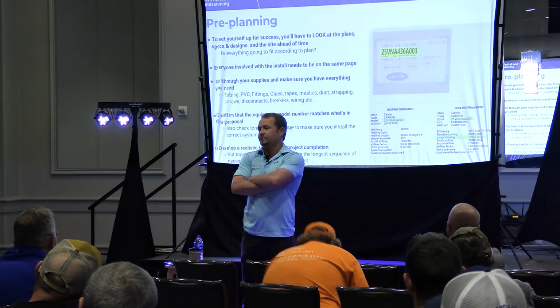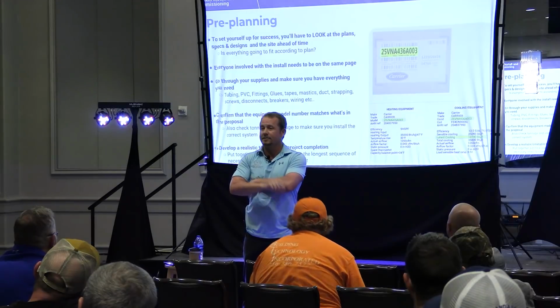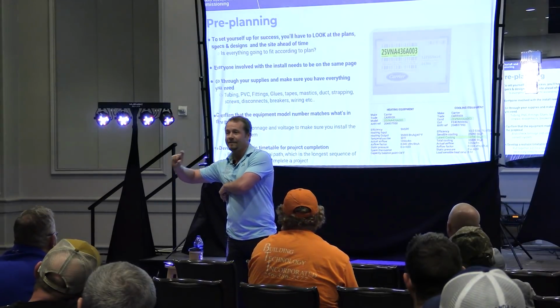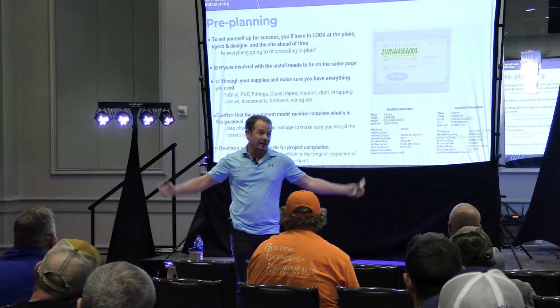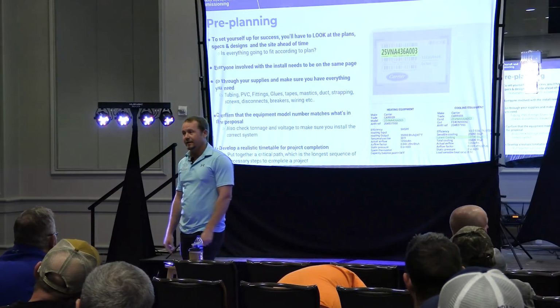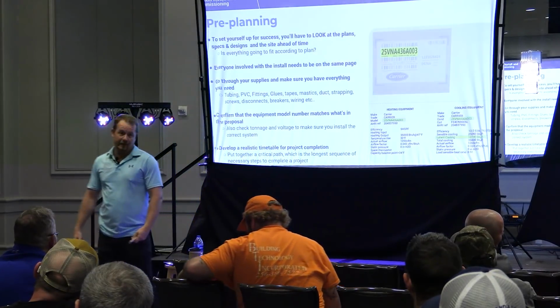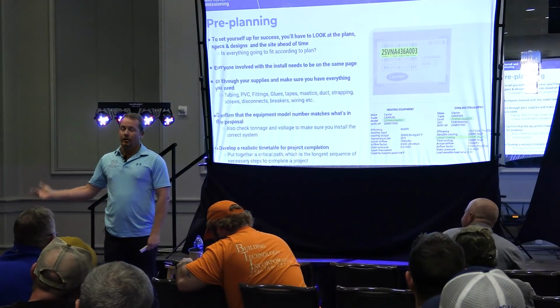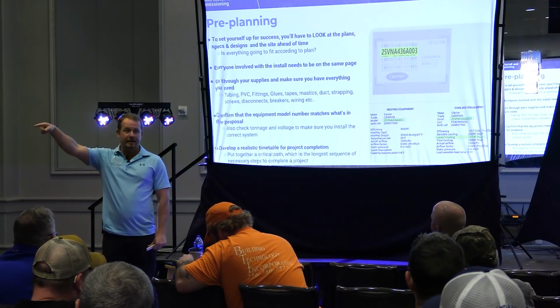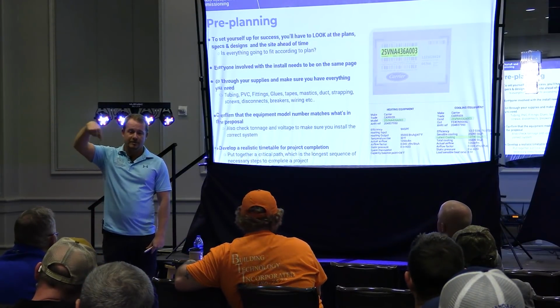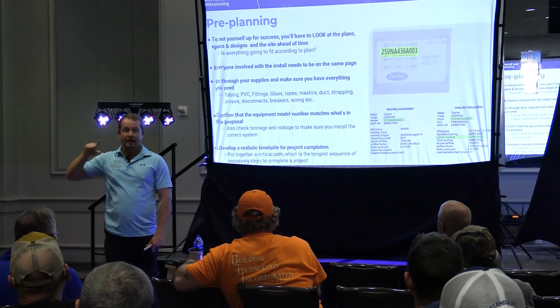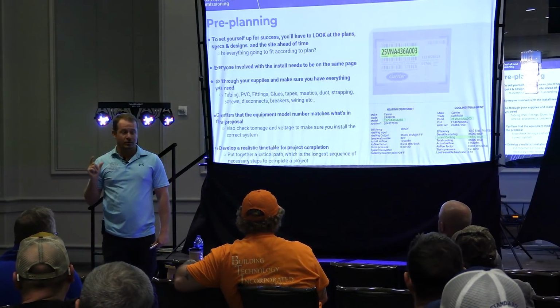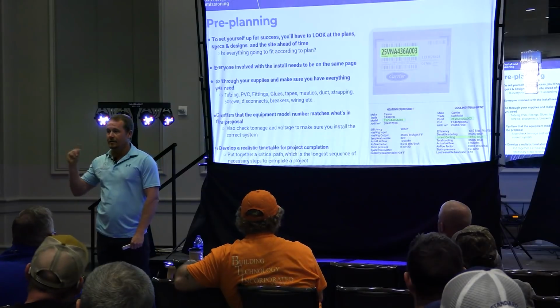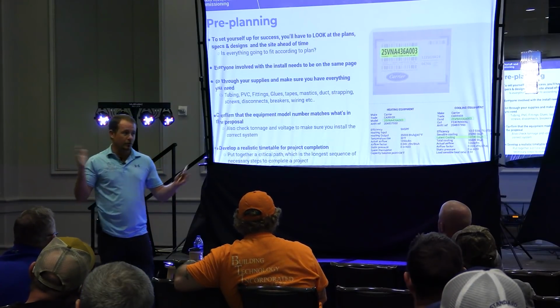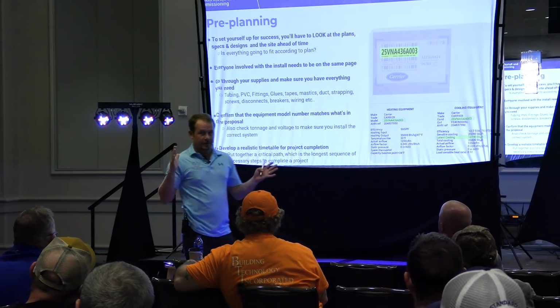Well, those of us who love these ductless systems, what do people say about them when they're trying to sell them? They're super efficient, right? 30 SEER. Well, how do they get that 30 SEER? They get 30 SEER by spinning the compressor slow. Do they drop the blower speed when they're spinning the compressor slower? Sometimes a little bit, but it's not proportional, because the controls are often independent of each other. The two aren't really talking in that same way.